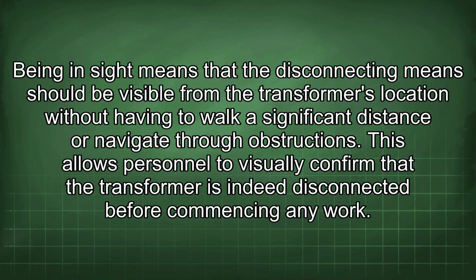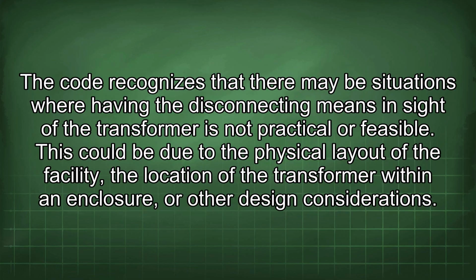Being in sight means that the disconnecting means should be visible from the transformer's location without having to walk a significant distance or navigate through obstructions. This allows personnel to visually confirm that the transformer is indeed disconnected before commencing any work. The code recognizes that there may be situations where having the disconnecting means in sight of the transformer is not practical or feasible. This could be due to the physical layout of the facility, the location of the transformer within an enclosure, or other design considerations.